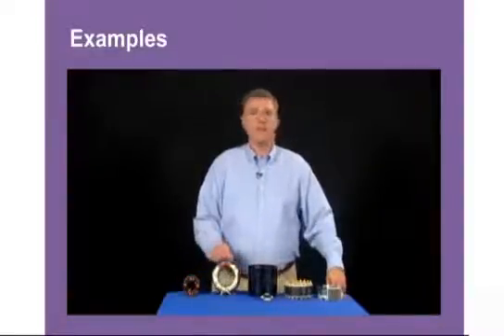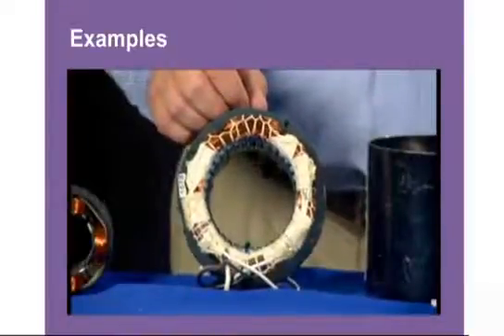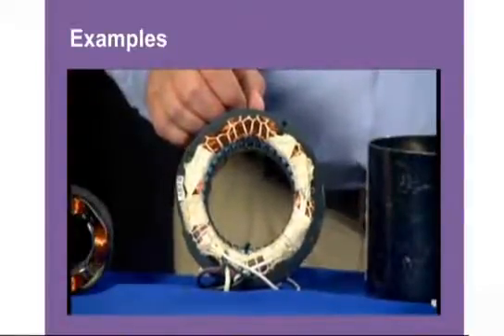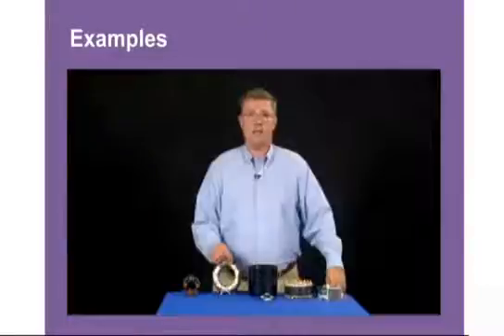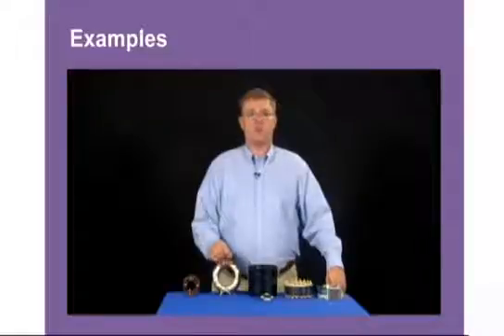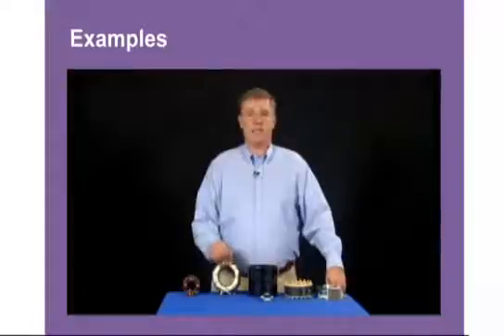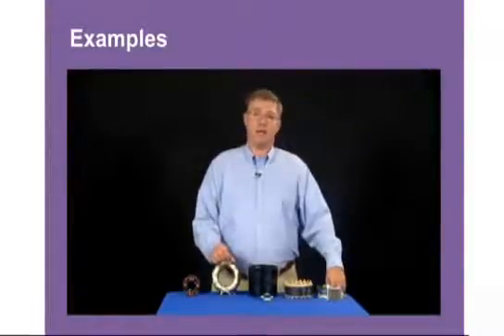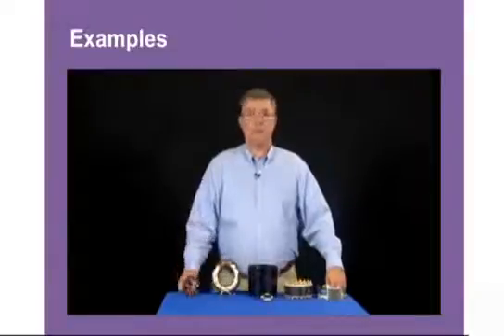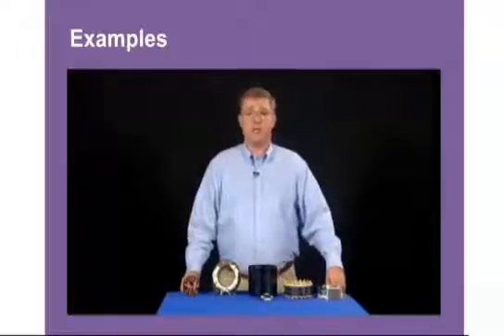The next type is a permanent split capacitor motor, or PSC. This type of motor has two sets of windings — an auxiliary start winding and a run winding — and both windings are always in the circuit. This makes the motor twice as efficient as a shaded pole motor. Any time it's possible to take a shaded pole motor out and replace it with a PSC, you should try and do it — for example, replacing a six-amp shaded pole motor with a three-amp PSC.